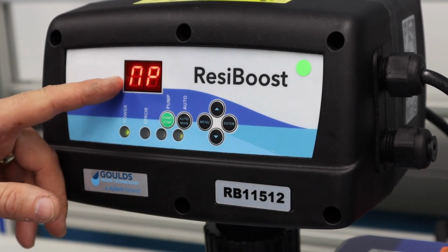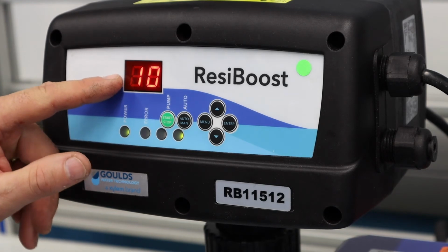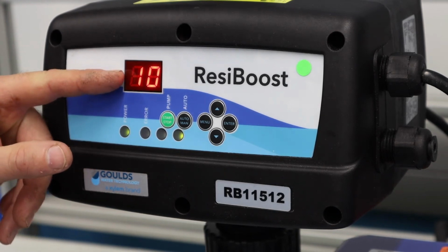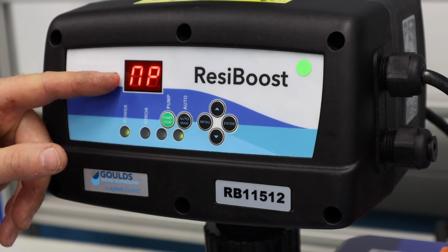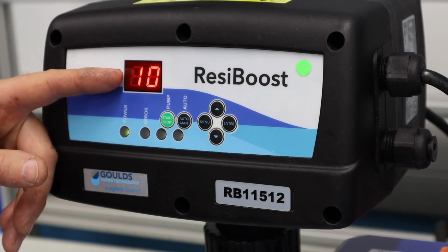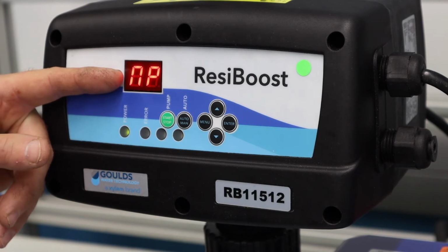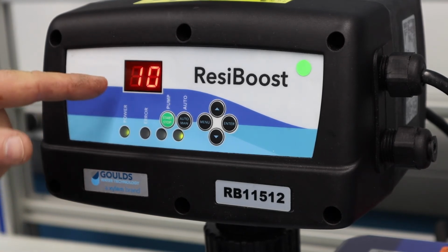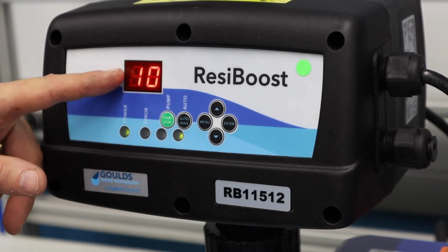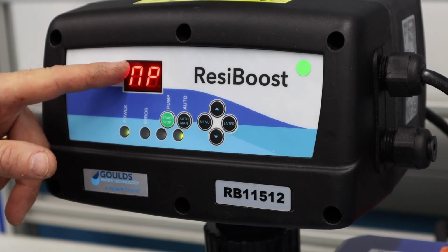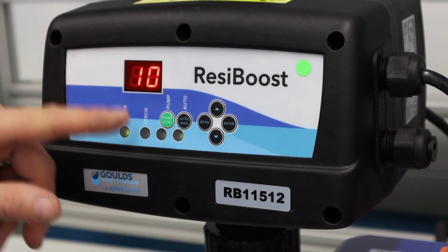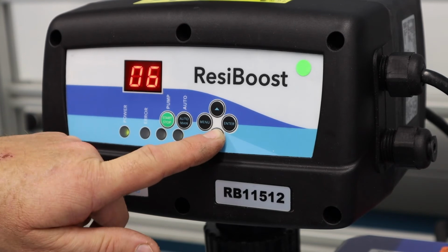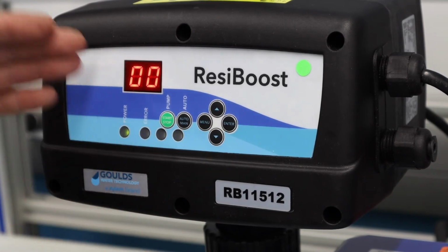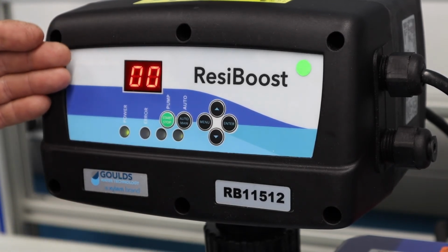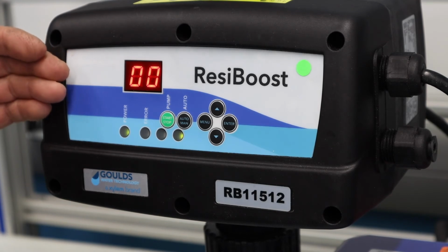Next is the NP, which is really minimum pressure. And again, that's another system protection. We can see here that the value is currently 10, and if the system pressure gets below this value, it's going to trigger an A4 alarm. So that can be altered, or let's say that you want to go down to 0. You don't want that low min pressure protection.